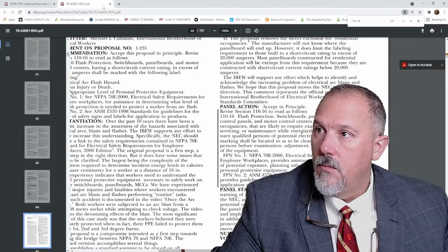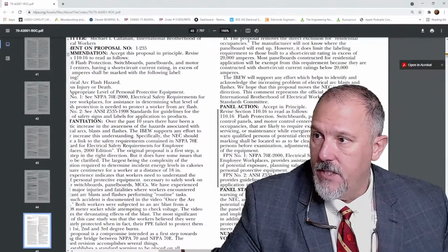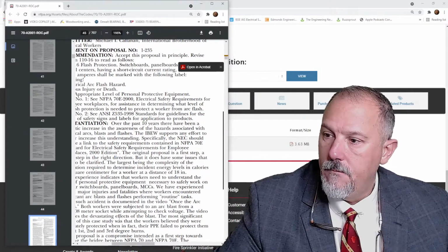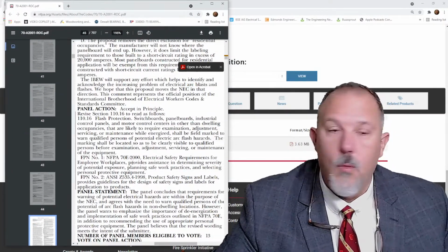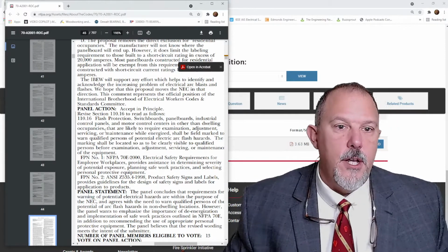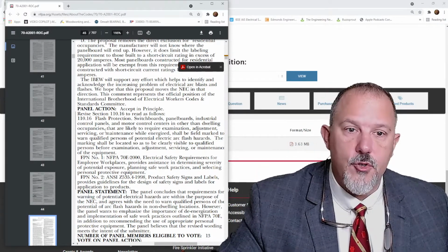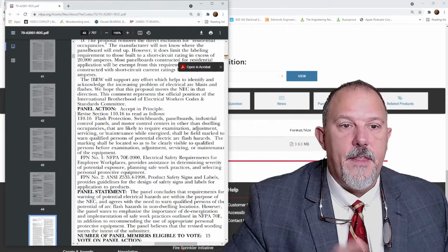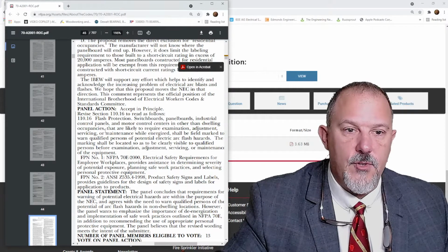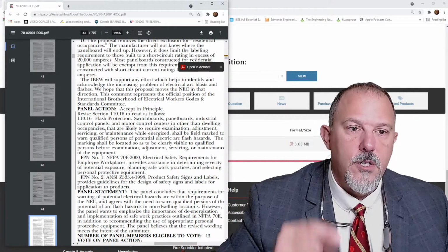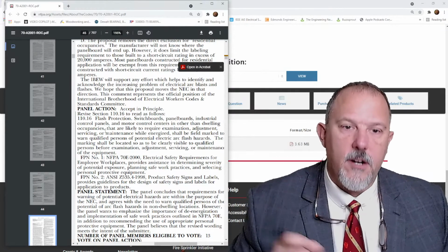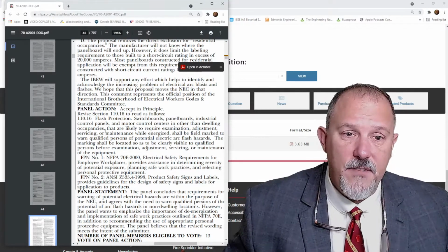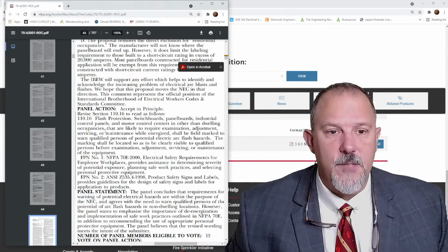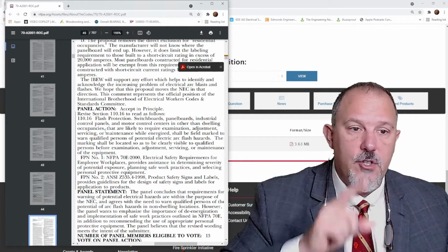The panel action, which is behind my head, which I can fix. Watch. Here's how we fix stuff like that. Panel action was to create a 110.16 flash protection. Switchboards, panel boards, industrial control panels, and motor control centers in other than dwelling occupancies that are likely to require examination, adjustment, servicing, or maintenance while energized shall be field marked to warn qualified persons of potential electric arc flash hazards. The marking shall be located so as to be clearly visible to qualified persons before examination, adjustment, servicing, or maintenance of the equipment. And they referenced 2 fine print notes.